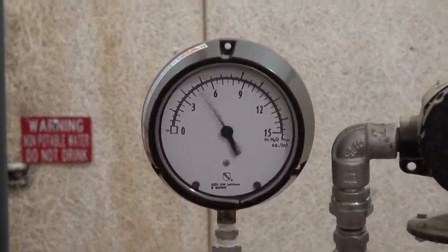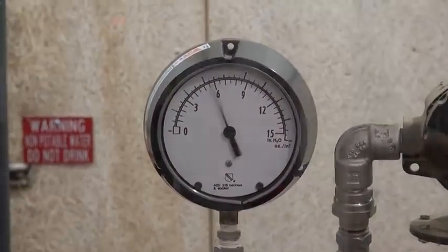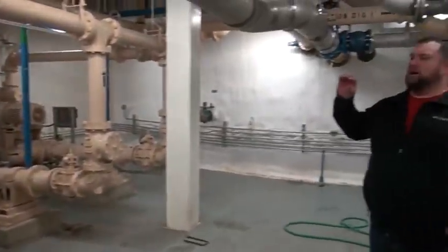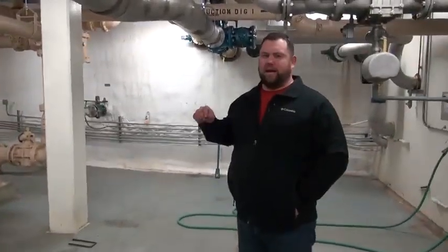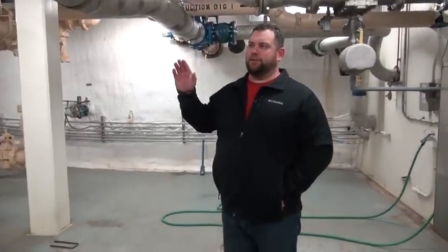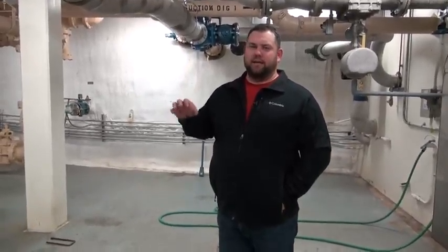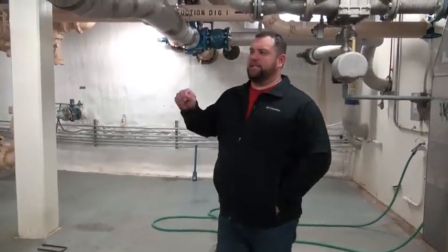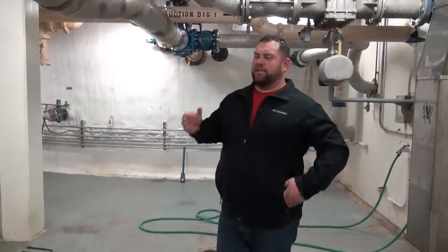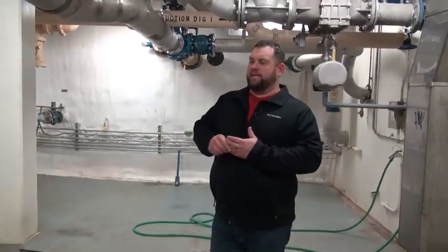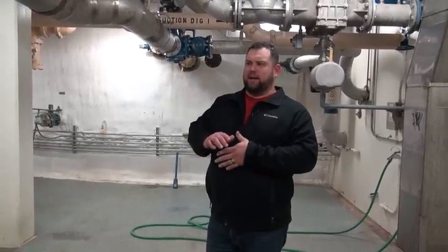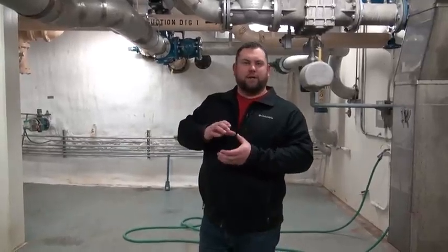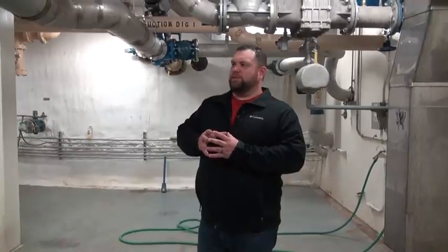Another thing we did recently, all in-house, was address a significant issue with our heat exchanger that heats our digesters fouling with what's called Vivianite, a hard precipitant that comes out of the sludge when the temperature swings. It's a combination of several nutrients, I think magnesium, iron, four or five different nutrients that combine to create this precipitant, and it was severely diminishing our heat transfer across the heat exchanger.